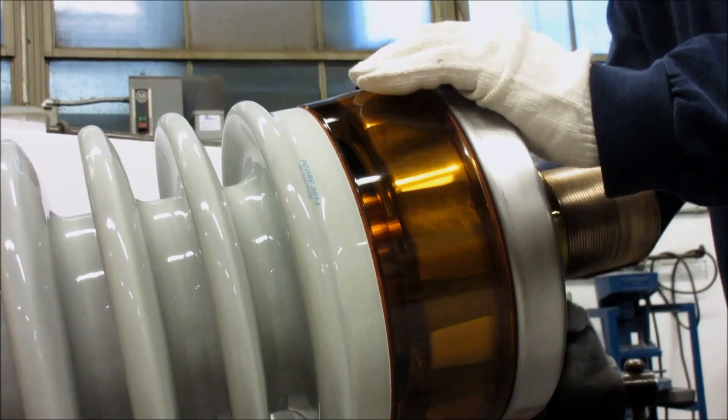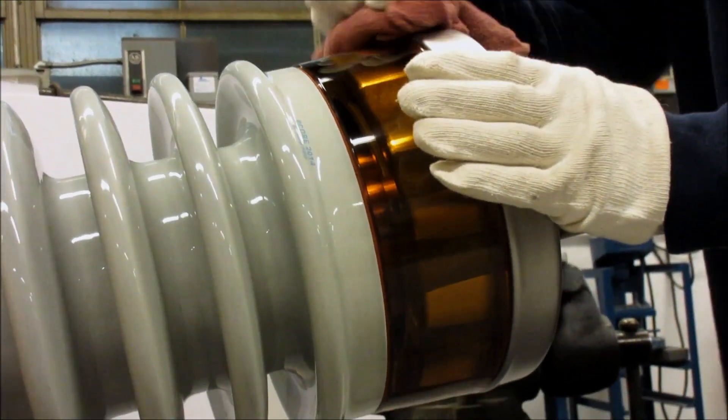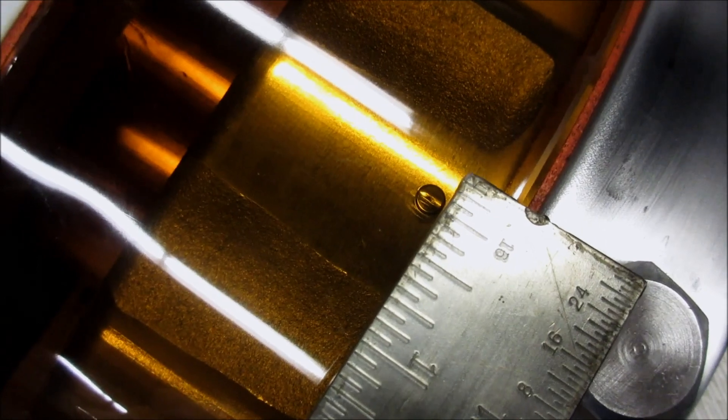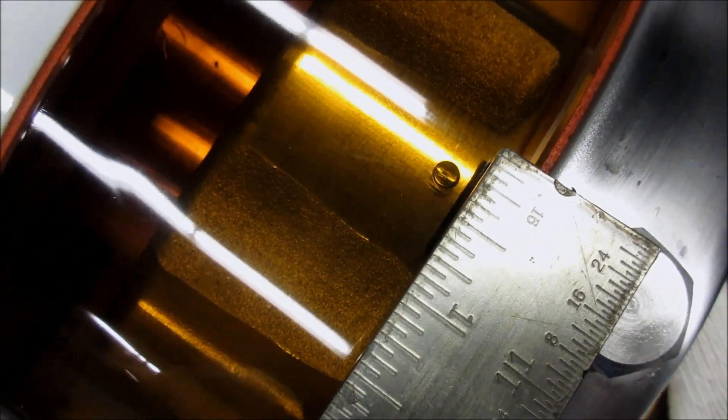If necessary, repeat steps five through six until some oil comes out of the fill hole in the top cover and any air bubble that remains in the top cover is less than one quarter inch in diameter.